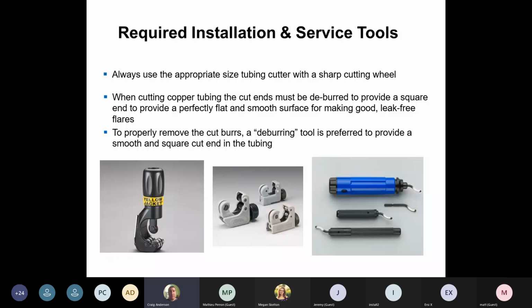Cutting tools. Make sure your cutting tools are clean. They're not rusted. Your wheel's going to cut right. We have a deburring tool. Deburring's a major thing when we're coming into mini splits. We want to make sure that we're deburring that copper before we're putting a flare on that. If we're not deburring it, what it's doing is giving us a double flare when we're putting a flare on that unit. When it's flaring down, it's giving it a double flare. So make sure you're deburring the copper.